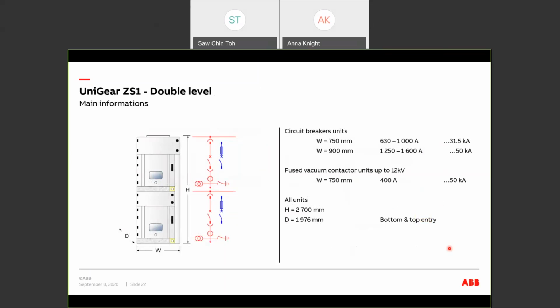Depending on the current running through the cubicles, we have 750 millimeter or 900 millimeter wide panels. Each of the circuit breakers or the contactors will have their own cable connections. So there are 2 segregated cable connections for the double feeders. Same as single level, we have the power cable option of coming either from the bottom or from the top of the cubicles.